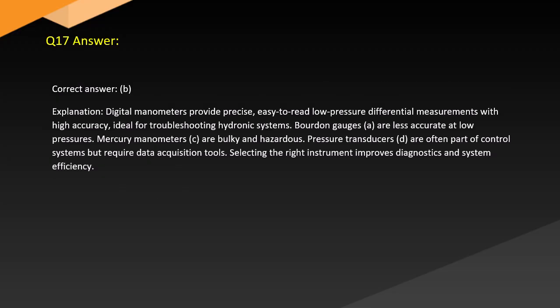Answer. Correct answer: B. Explanation: Digital manometers provide precise, easy-to-read low-pressure differential measurements with high accuracy, ideal for troubleshooting hydronic systems. Bourdon gauges (A) are less accurate at low pressures. Mercury manometers (C) are bulky and hazardous. Pressure transducers (D) are often part of control systems but require data acquisition tools. Selecting the right instrument improves diagnostics and system efficiency.